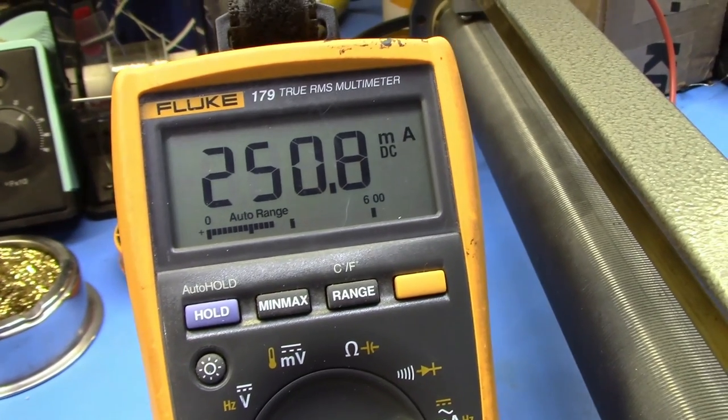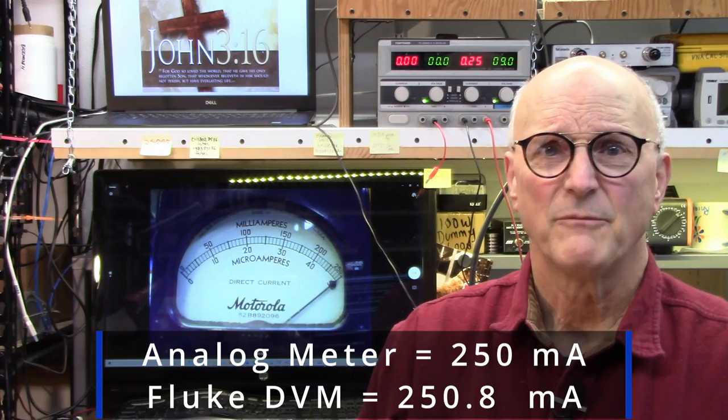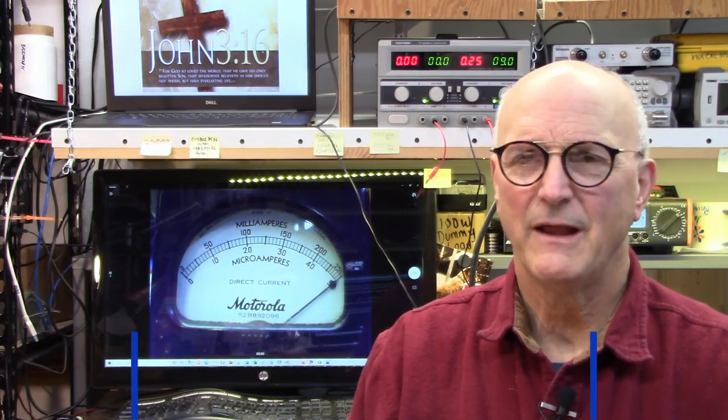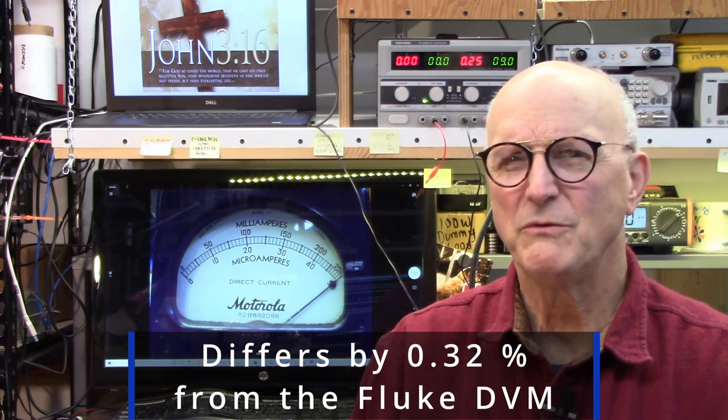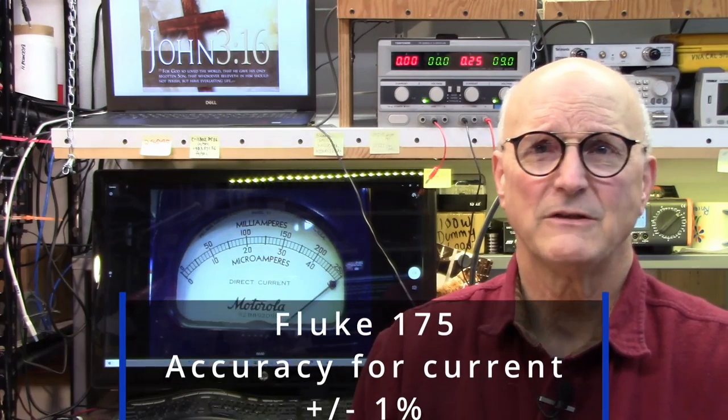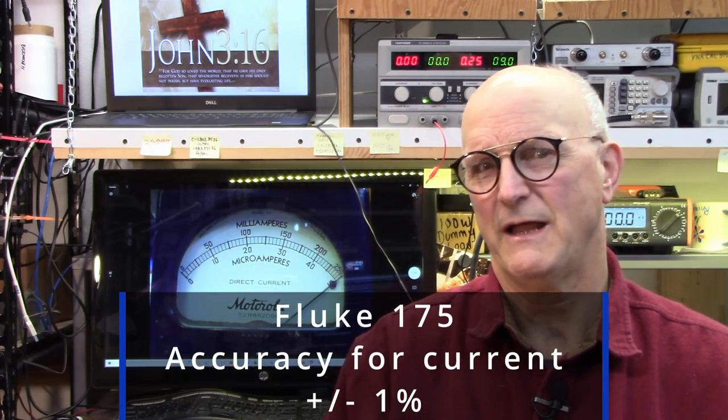250.8 milliamps. So when I got my meter all the way up to full scale, 250 milliamps according to it, my DVM read 250.8 milliamps. So that means that my analog meter, which I just set up with this shunt and everything, differs from my DVM by 0.32%. That's pretty doggone good. Now I'm using my Fluke 175 to measure the current. And according to the manufacturer's specifications, it is to be accurate within 1%.